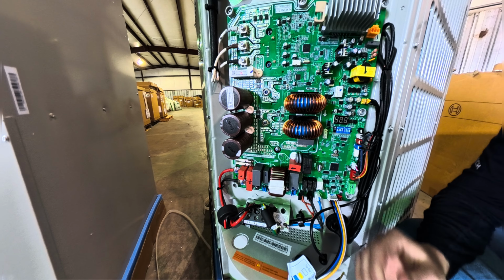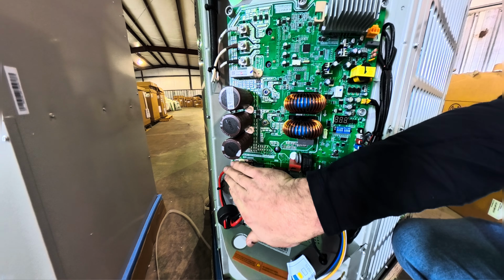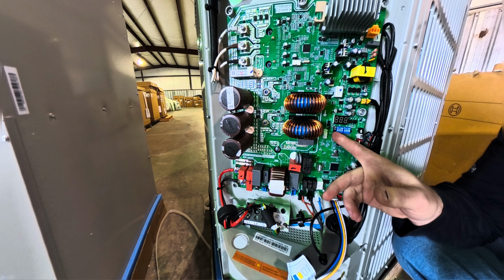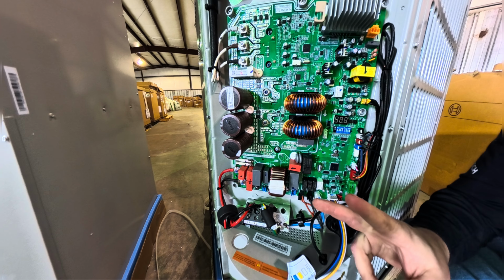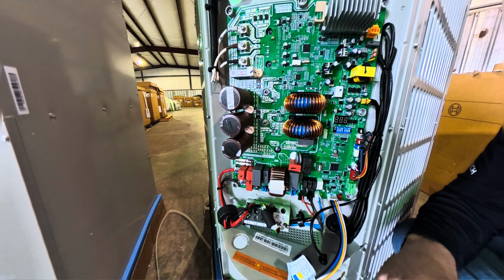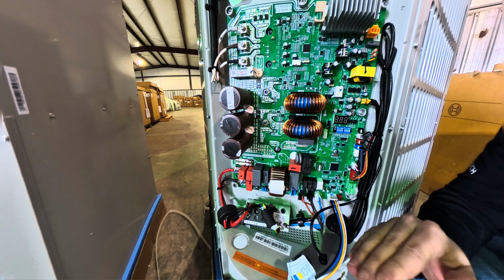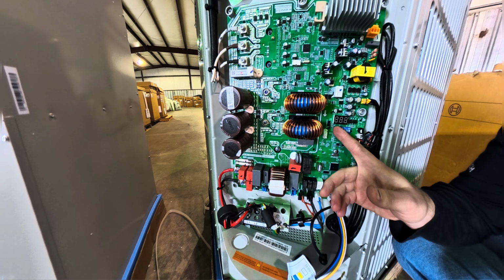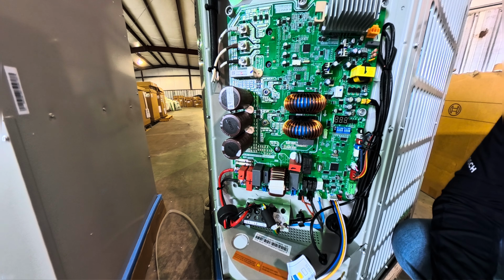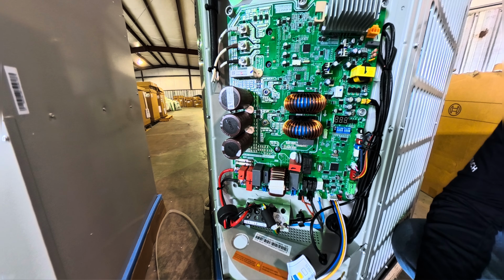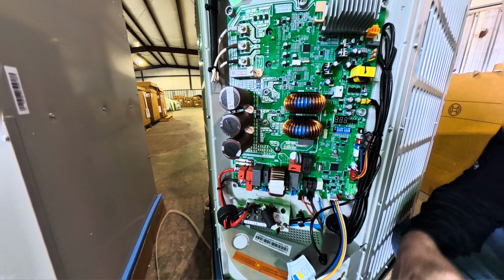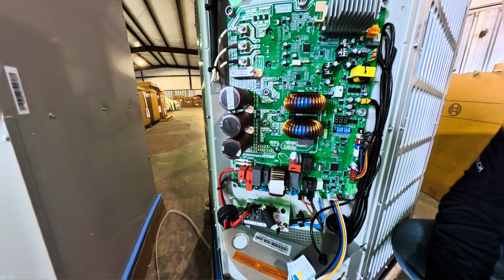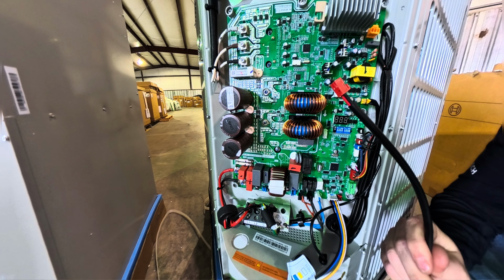We have a DIP switch bank over here, high voltage here, DIP switch bank over here. This is for your capacity. So they have 2 outdoor units. It is a 3-ton and a 5-ton. If you wanted to make this a dedicated 4-ton, you would switch this down, dedicated 5-ton, leave it up. We shouldn't have to touch that because it's looking at our pressures and looking at our temperatures to see what speed it needs to run. So you will have no problem pairing this on a 2-ton air handler if you wanted to. It is going to ramp up and down based on that coil temperature, based on the airflow of that air handler. So we won't have to change capacity. We don't really have to mess with dip switches out here unless we're wiring this in communication mode.